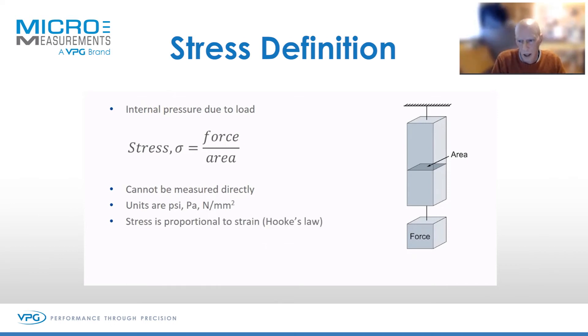You can calculate the stress because stress is proportional to strain in Hooke's law, which many of you would have done at school or university. We measure strain and can calculate the stress if we know the material properties. We have strain gauges measuring strain, and we use that to calibrate whatever units we wish.